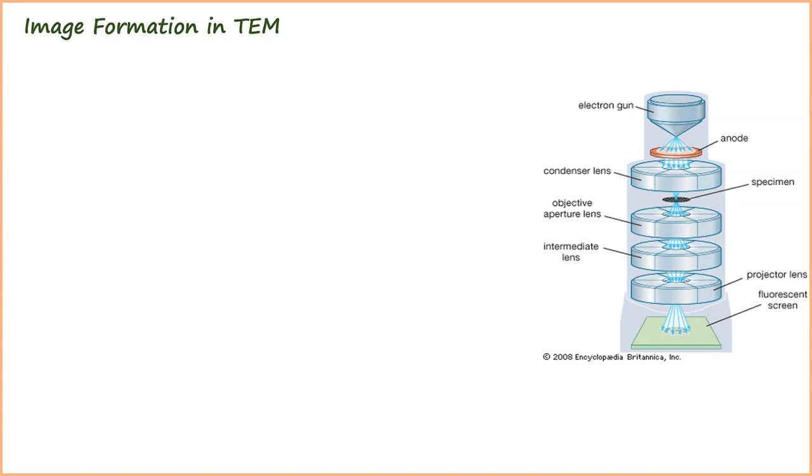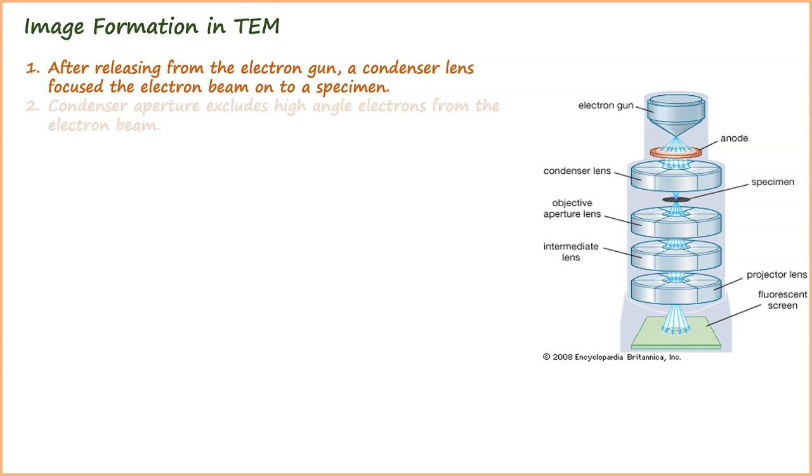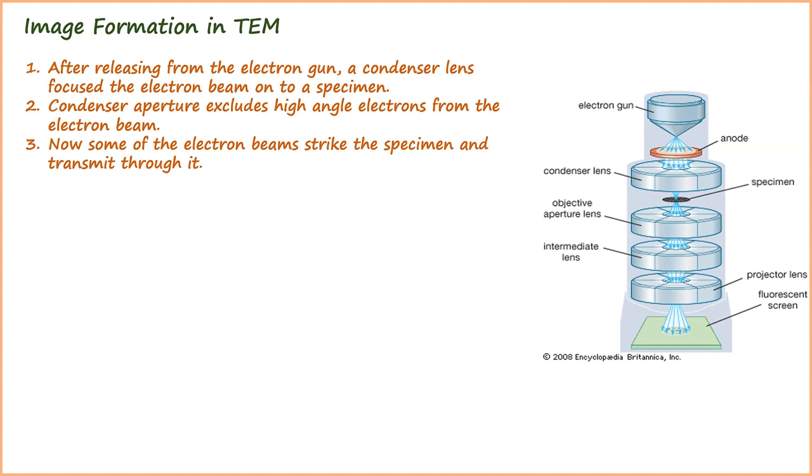Now we will discuss image formation in transmission electron microscope. After releasing from the electron gun, a condenser lens focuses the electron beam onto a specimen. Condenser aperture excludes high-angle electrons from the electron beam. Now some of the electron beams strike the specimen and transmit through it.